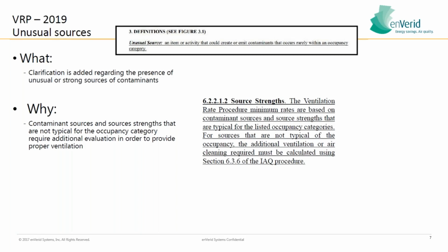An unusual source is an item or activity that could create or emit contaminants that occur rarely within an occupancy category. So I mentioned earlier designing buildings next to roadways, next to airports, etc. Those create or emit outdoor contaminants that occur rarely within an occupancy category. So for those sources, if you're designing a building there or have a building there, you actually must use the indoor air quality procedure according to ASHRAE 2019. This is a massive change for the entire industry.